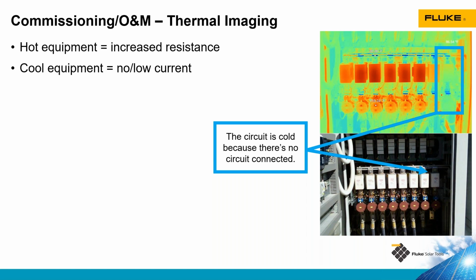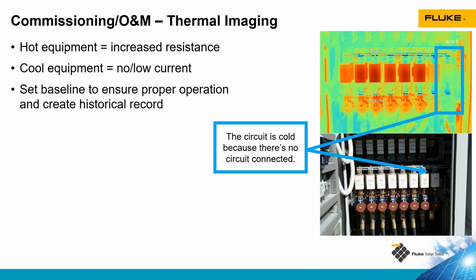An example here in this picture, we've got a piece of equipment here. That circuit on the right is a much cooler temperature than the rest of the circuits. And that's because there is no circuit connected to that terminal. If this was a combiner box, that may indicate that there is a disconnect somewhere in that string of modules.